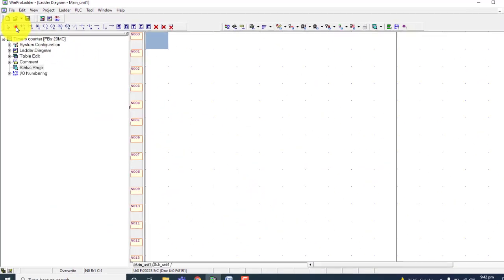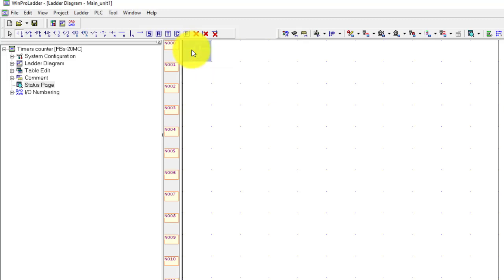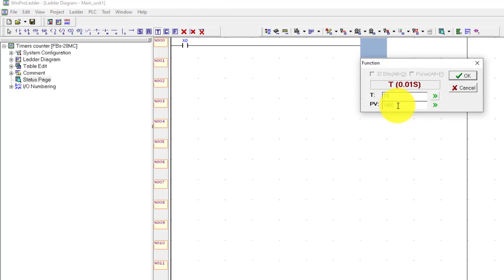Let's start the programming of the timer. Use input X0 and timer T0. This is the 0.01 second base timer. So if I want a delay of 10 seconds, I have to multiply by 1000. It will automatically give a 10 second delay.